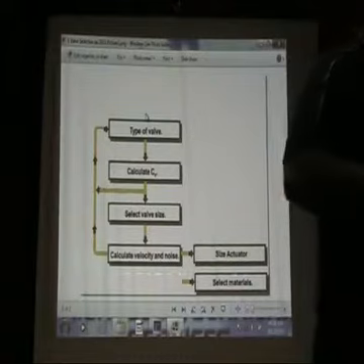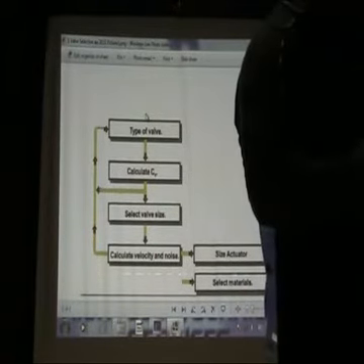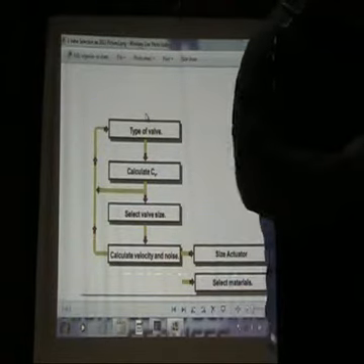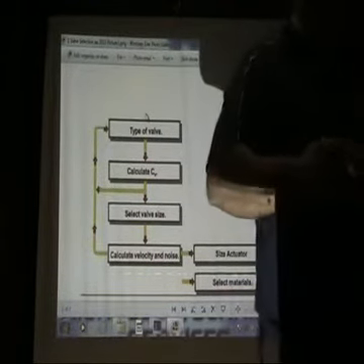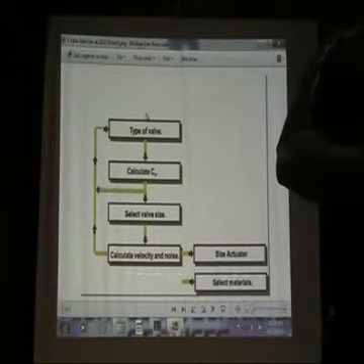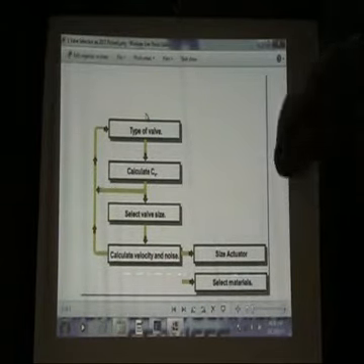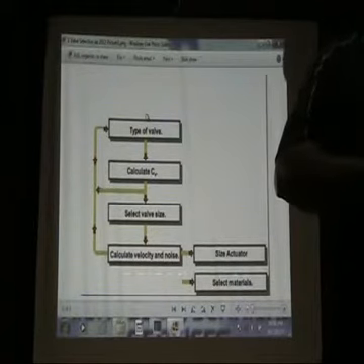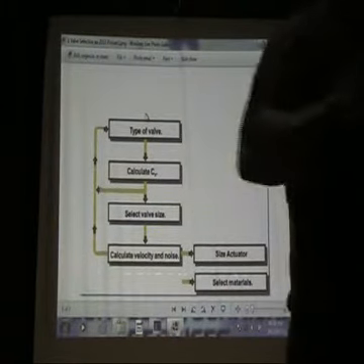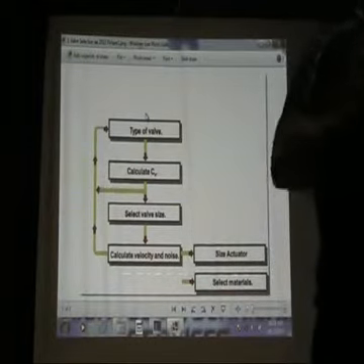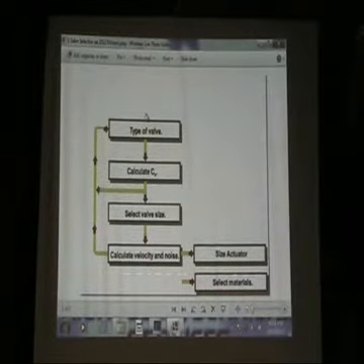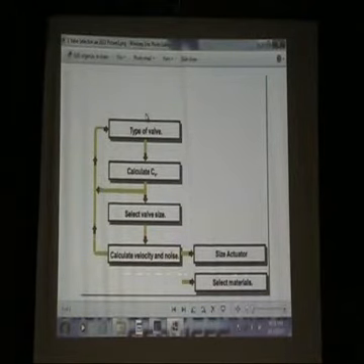You said eccentric. Should we plug? To be honest, I've been in the valve industry for 20 years and I haven't sold one plug valve. I'm nothing against plug valves. The plug valve is the same as the ball valve, but it's a plug. It's a long, tapered plug with holes in it. It just turns like a ball. It's a 90 degree, quarter turn valve. So it's a tapered ball valve. There are two types: non-lubricated and lubricated plug valves.